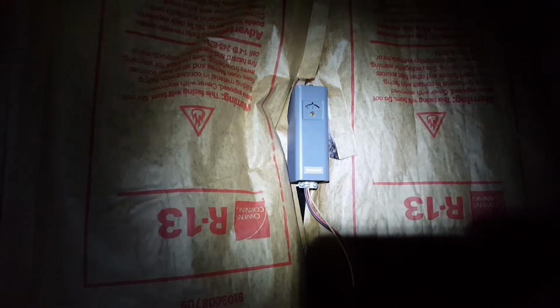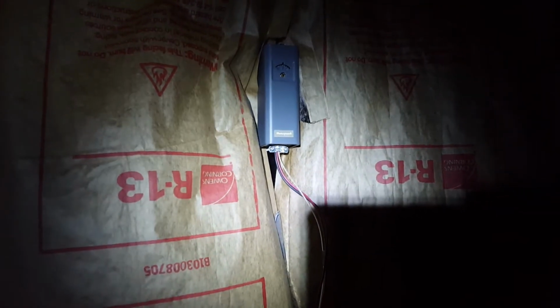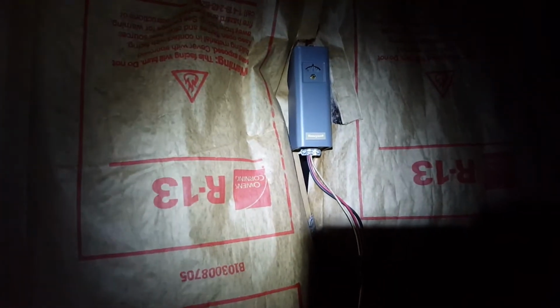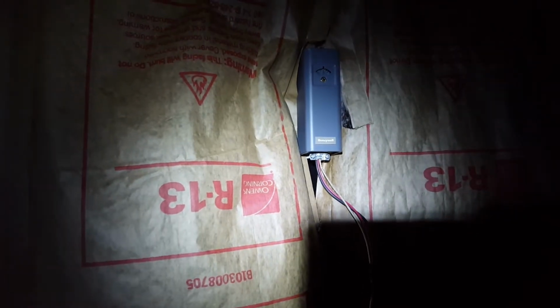So the second moving part, if you want to call that, is the Aqua Stat. The Aqua Stat is adjustable, and what that does is measure water temperature. When the water drops below a certain temperature, those wires right there signal the fan out front to kick on, and then that fan stokes the fire.